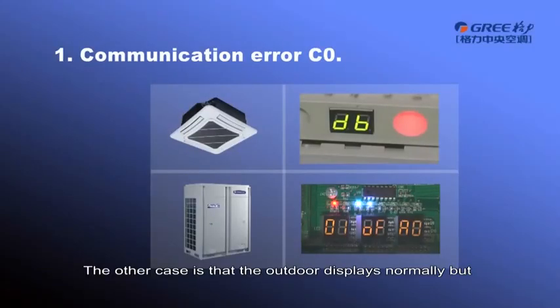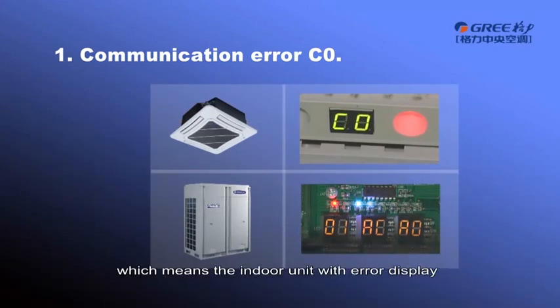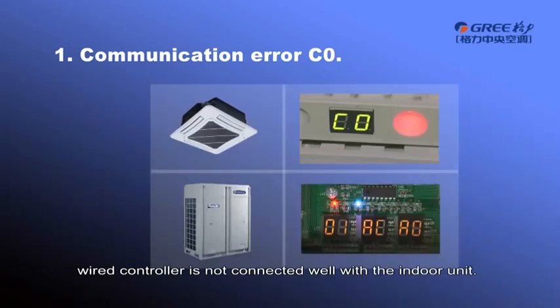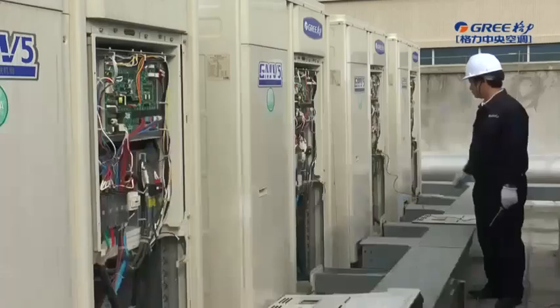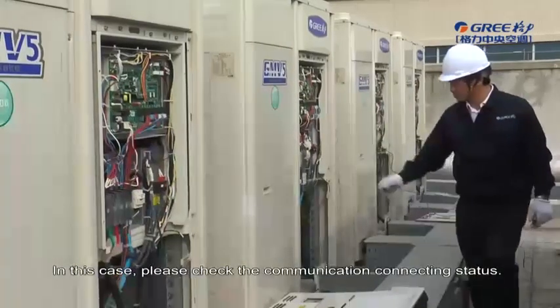The other case is that the outdoor display is normal, but some indoor units display C0. This means the indoor unit with the error display is not connected well with the main communication cable, or the controller is not connected well with the indoor unit. In this case, please check the communication connecting status.